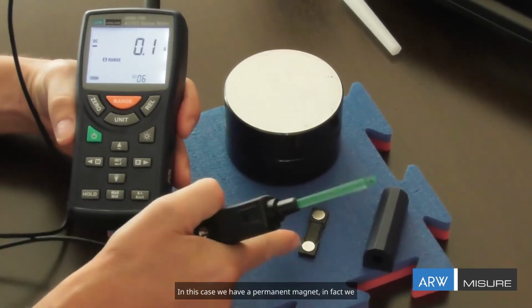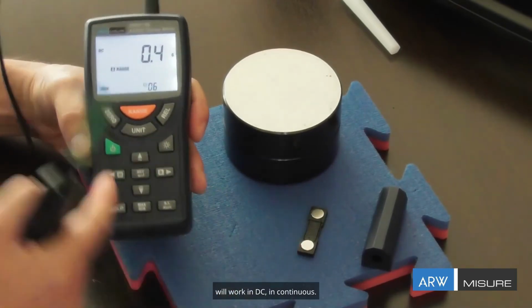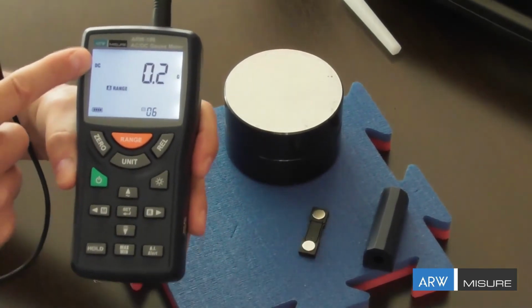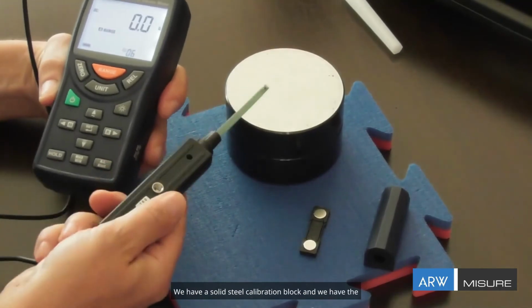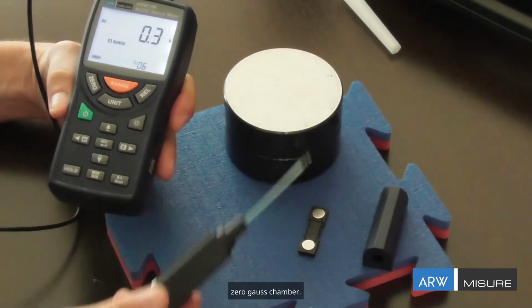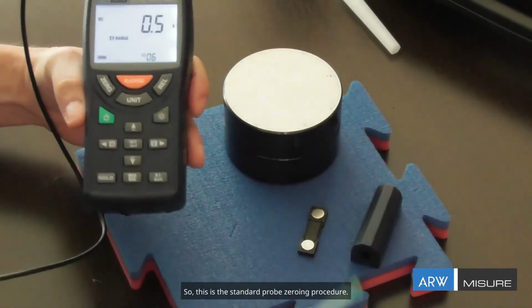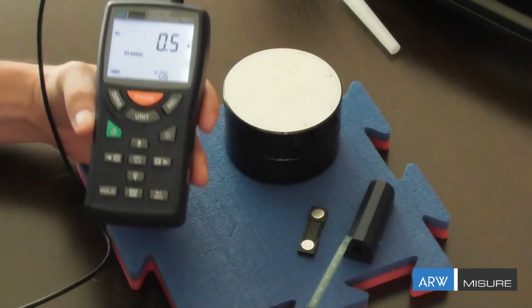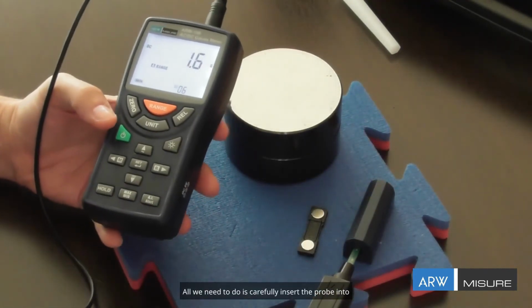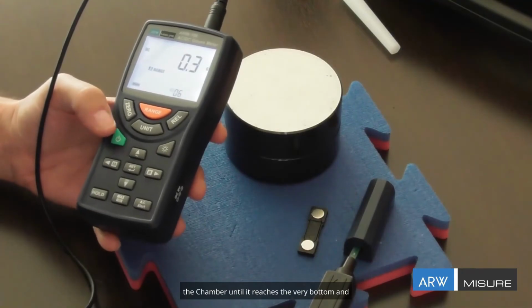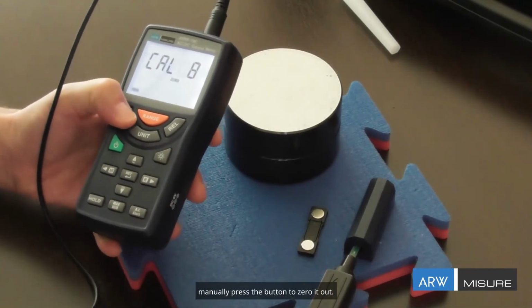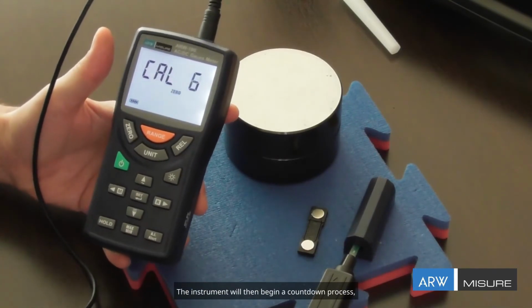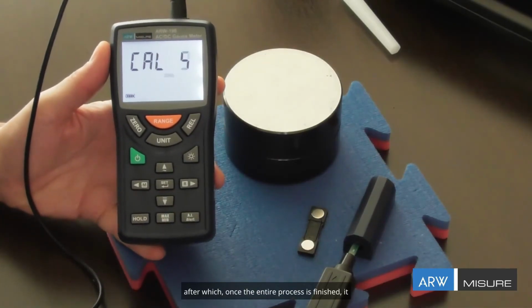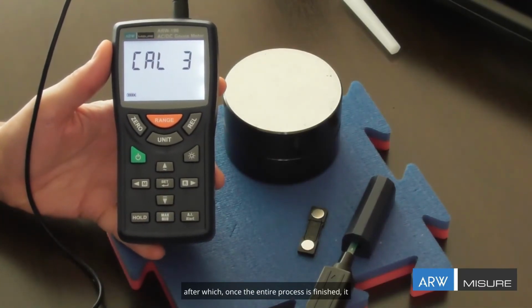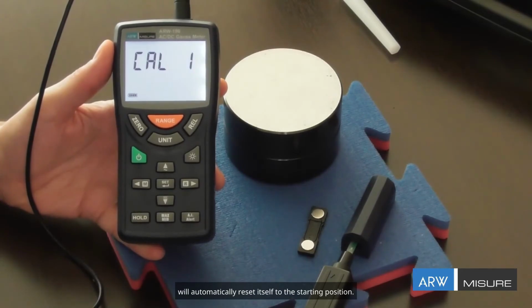In this case, we have a permanent magnet. In fact, we will work in DC, in continuous. We have a solid steel calibration block, and we have the zero Gauss chamber. So this is the standard probe zeroing procedure. All we need to do is carefully insert the probe into the chamber until it reaches the very bottom and manually press the button to zero it out. The instrument will then begin a countdown process, after which, once the entire process is finished, it will automatically reset itself to the starting position.